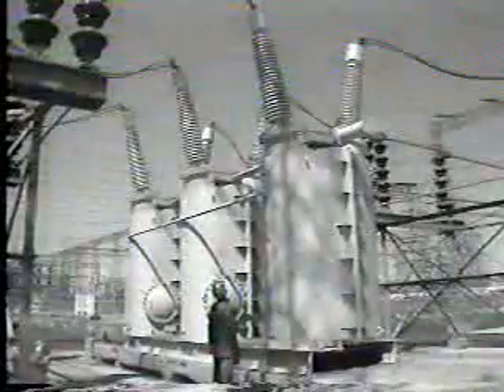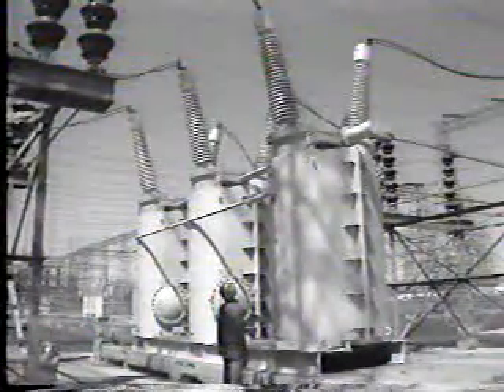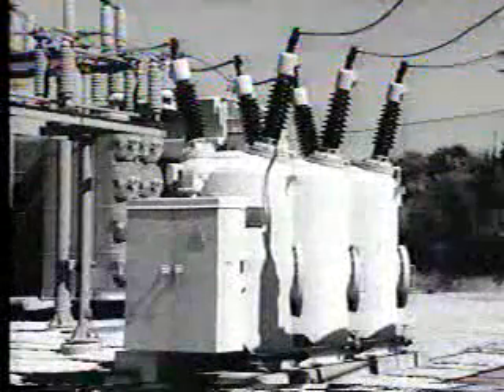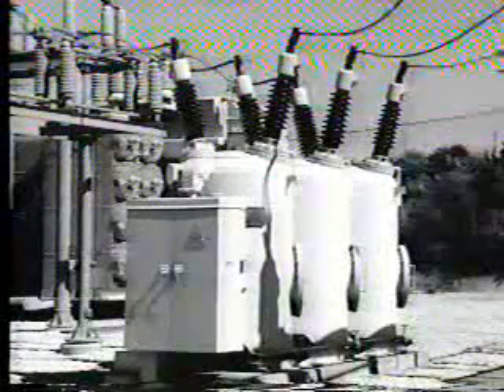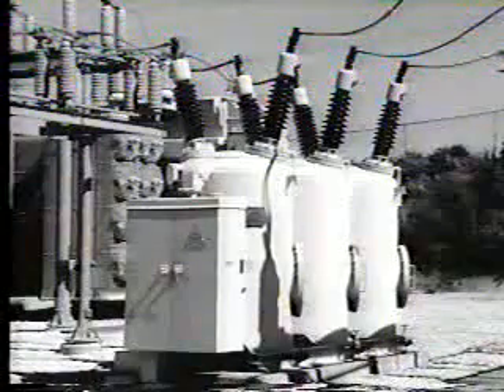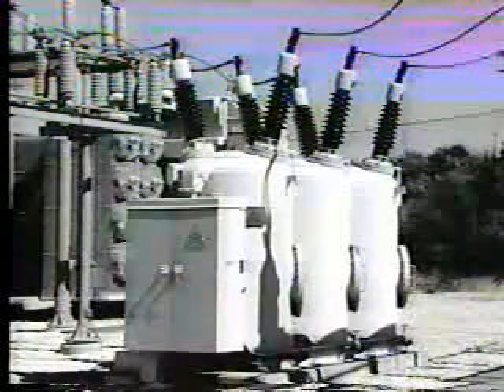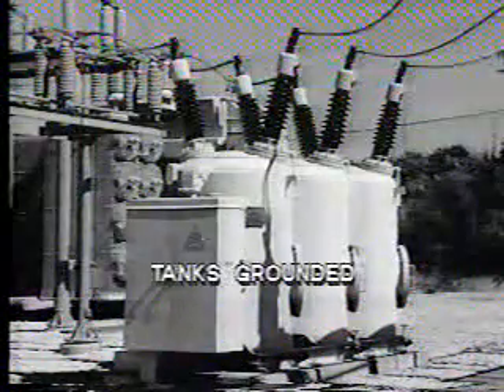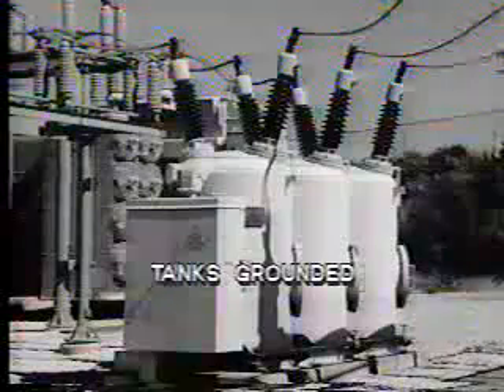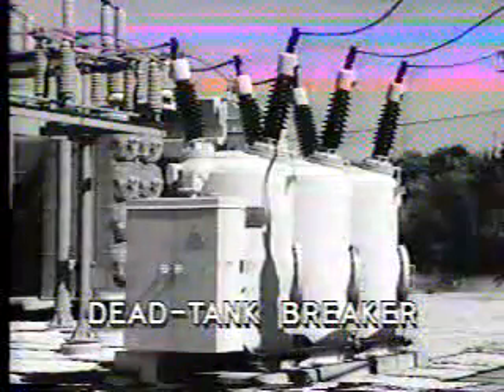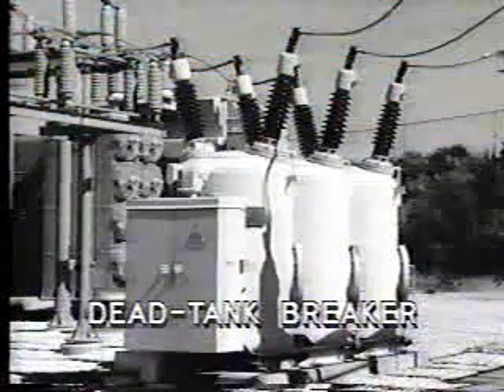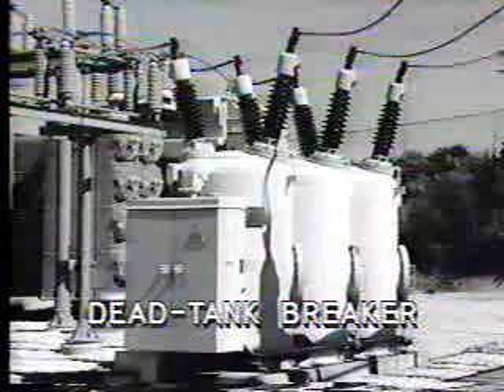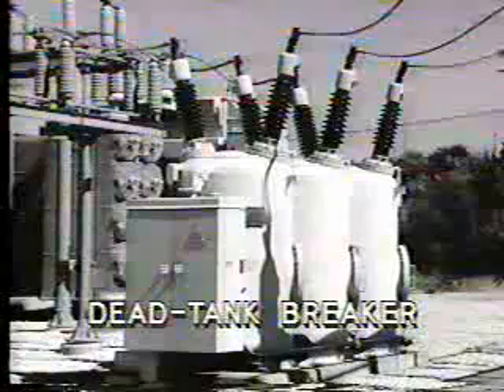Various methods are used to quench the arc inside the interrupter, depending upon the size and voltage of the breaker. The quenching medium may be oil, as in the case of this 132 kV oil circuit breaker. In this type of breaker, all three phases are immersed in oil tanks, and the tanks are grounded. This is known as a dead tank breaker. We mention it here because the item does have some significance in protection, as you'll see in later tapes.